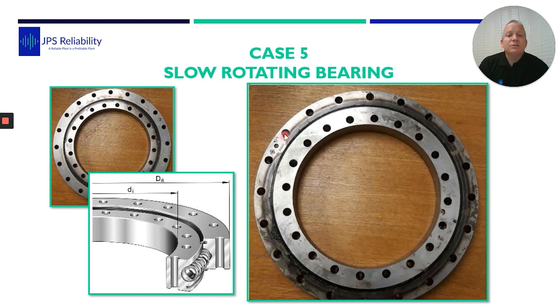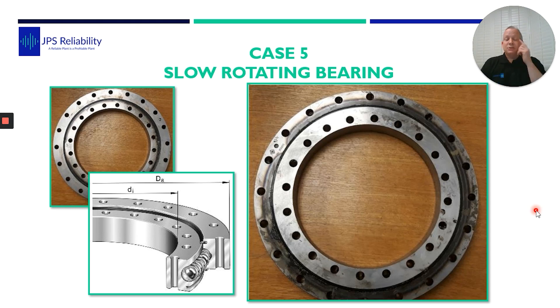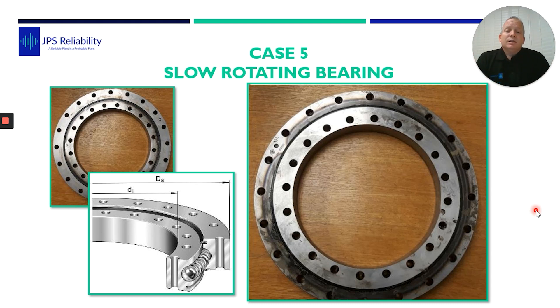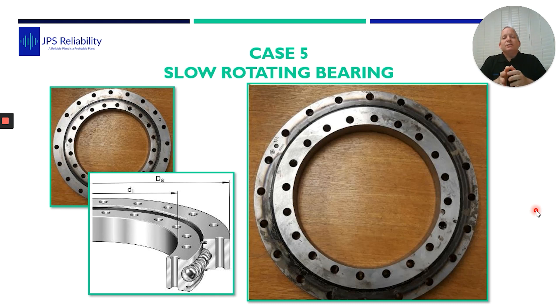This is the four-point contact bearing — both the outer and inner race can rotate. The marks here are actually part of the manufacturing process, not damage from the bearing. In this particular case, the slurry pot shaft goes to the middle and the outer race is stationary while the inner rotates. There was a lot of doubt about whether we could pick up a defect with vibration analysis because it was going so slow, but sampling at high rates gets you into the ultrasonic range anyway.